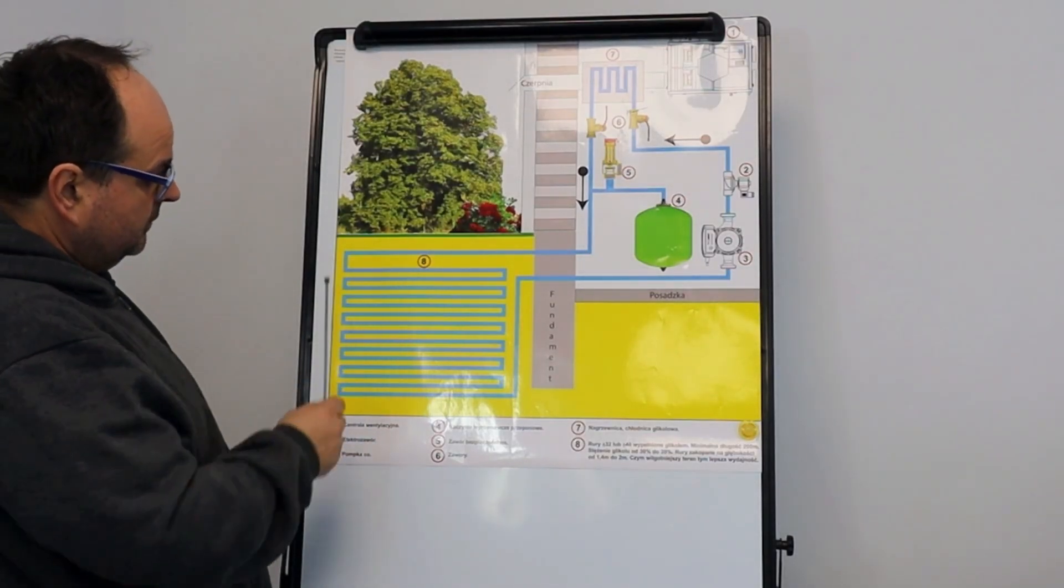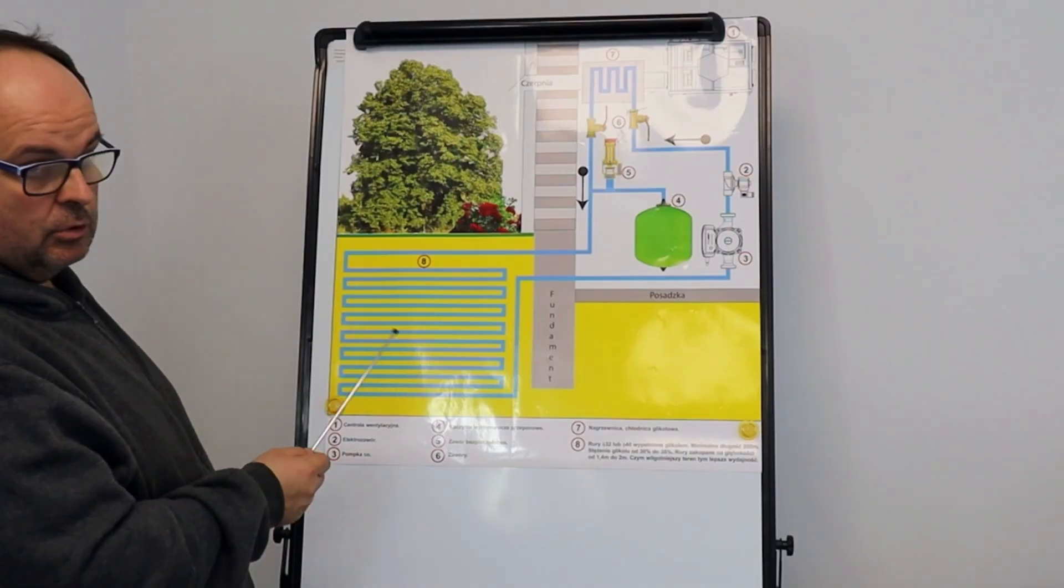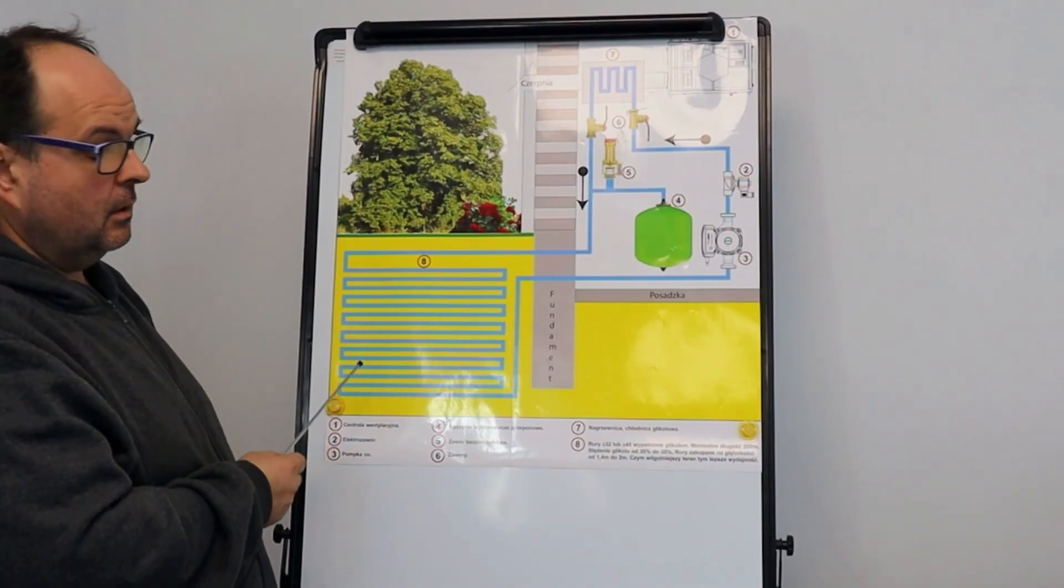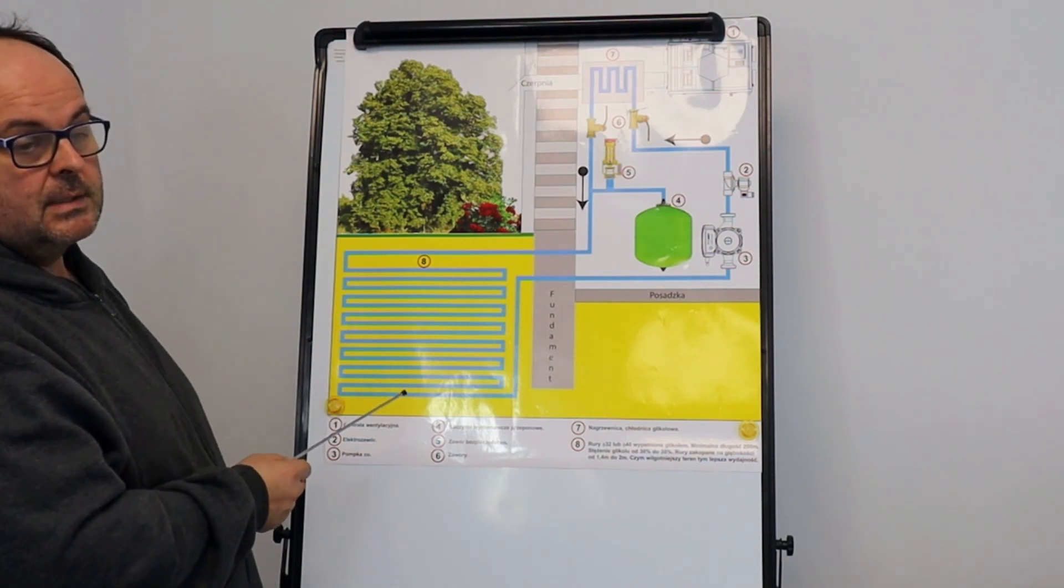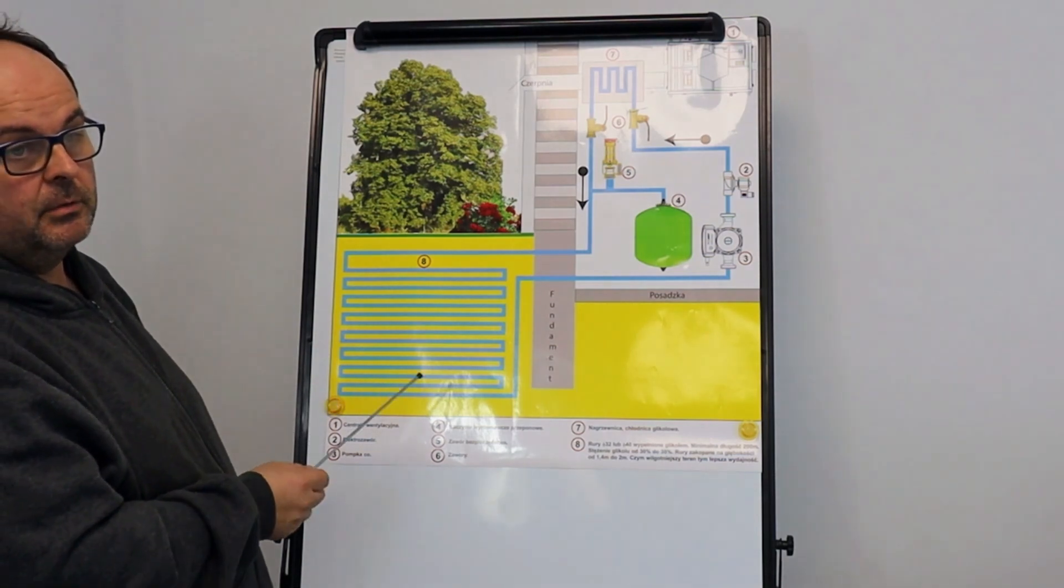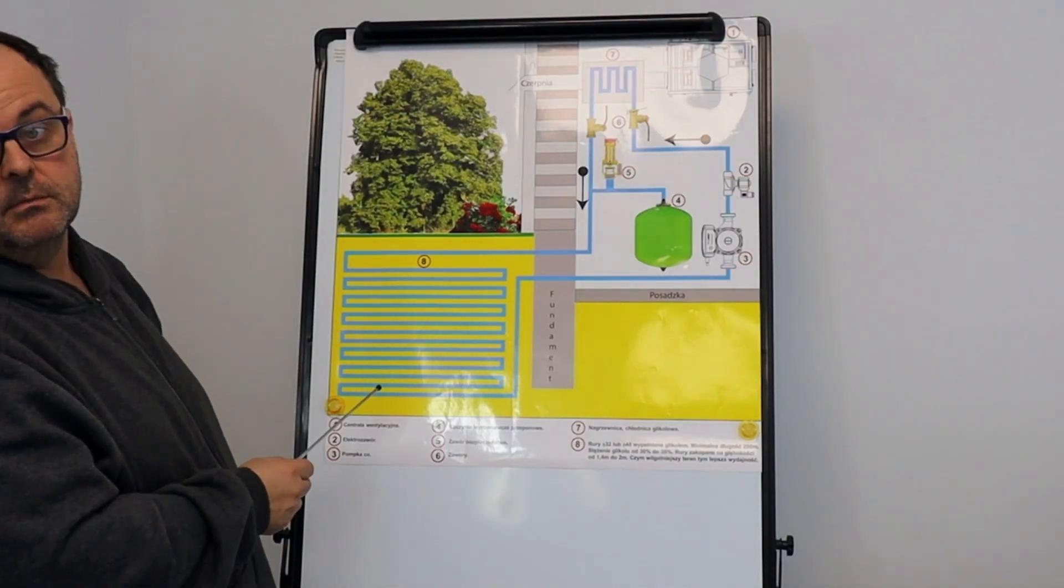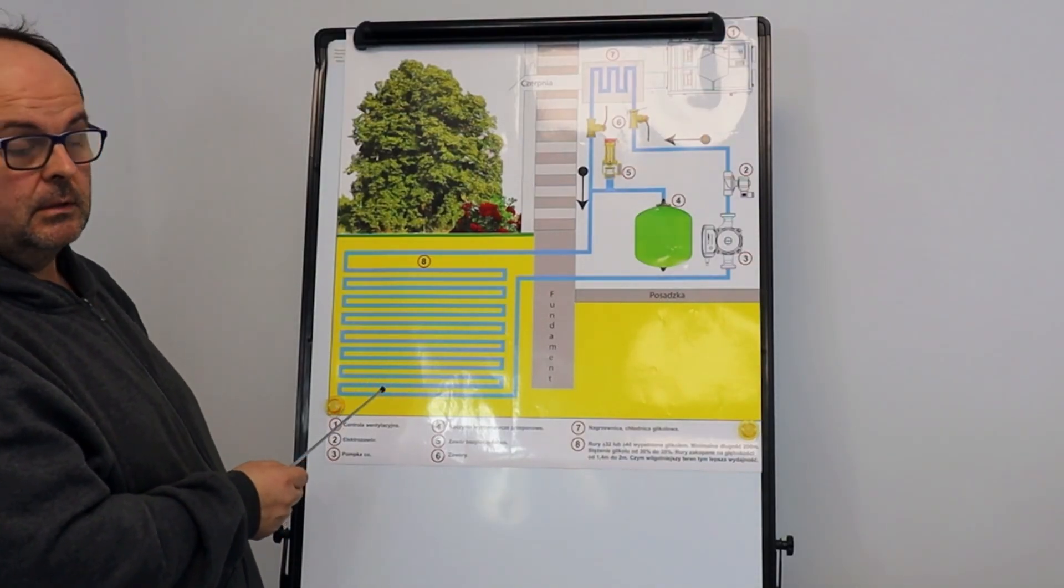But remember that with the glycol exchanger power, let's say at 200 meters of those tubes, depends on the environment, but on average we achieve two, two and a half kilowatts. With a regular air system where air flows through these tubes, we get one kilowatt more.